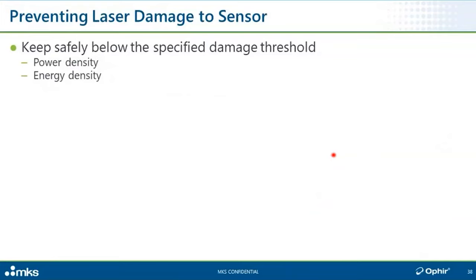Next challenge, preventing damage. First and most obvious solution step is to make sure that you're operating below the specified damage threshold of your sensor. That means keeping below the maximum rated power density, and if you're working with a pulse laser, keeping below the specified energy density. I want to emphasize that, because a lot of times people don't think about the energy density, because they're only measuring the power. But even if I'm not measuring energy, too much energy density can still damage my sensor. So it's something you want to be aware of.